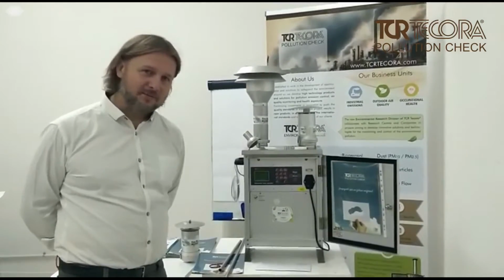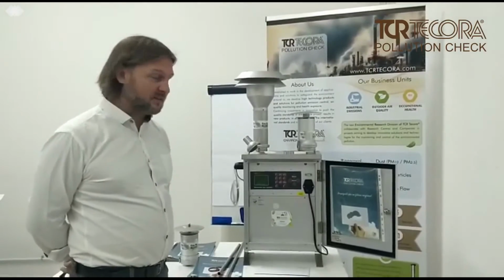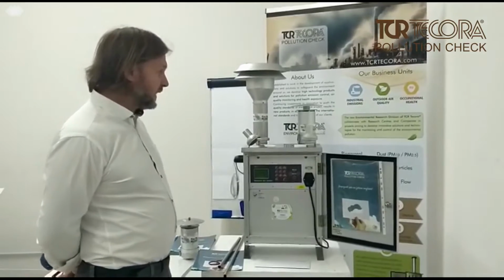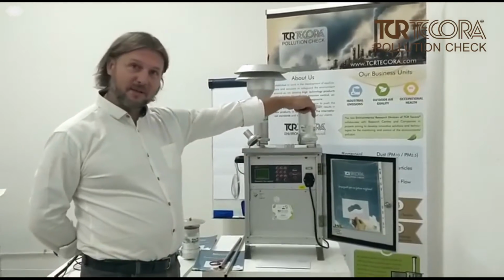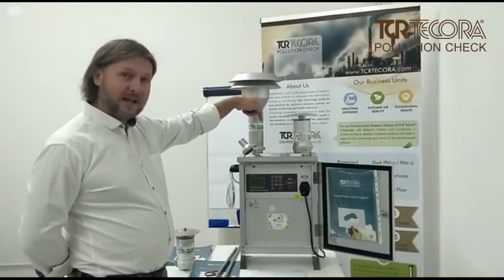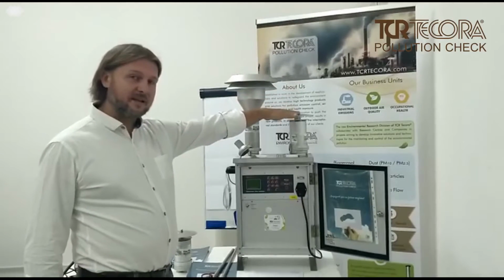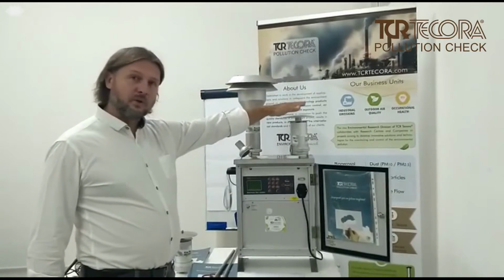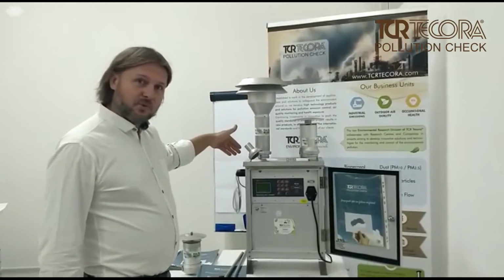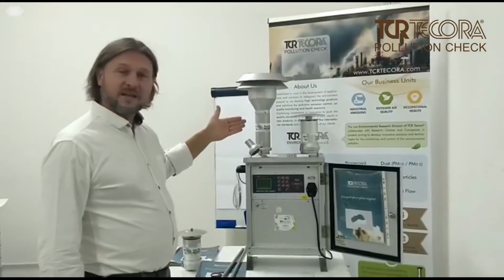Hello guys, my name is Marco. This is our EchoPM instruments series. This is a low volume sampling system. It can be used with a single head, with a single line sampling, or with a two-line sampling, not simultaneously, or three-line. So we can have, for example, sampling line 1 with the PM10 head according to the European method, or if you want, sampling line number 2 with the USA EPA head for PM10, or with the cyclone for PM2.5.